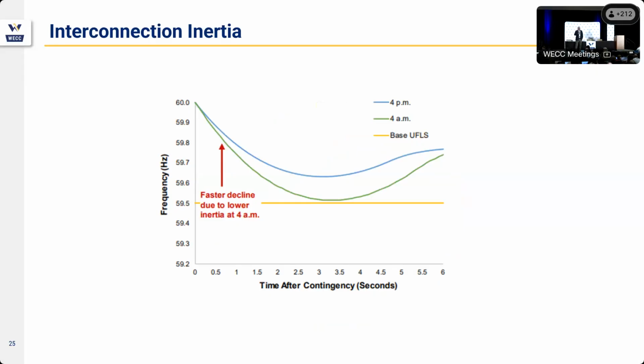Today, we see time to nadir in 4 seconds, which means the batteries are arresting the nadir. We're seeing megawatts being injected in the first half second, and they're changing where the bottom is because they're injecting megawatts so quickly. It's one of the problems we're actually having with BAL3.